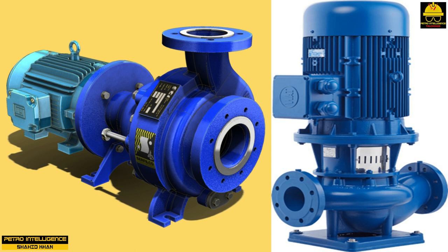Horizontal pumps are the most common type found in industry. However, vertical pumps are more compact, winterize better, and have a lower installation cost. Vertical pumps work well with liquids that are near their bubble point temperature. The lower impeller usually is located below ground level, which provides additional net positive suction head available, NPSHA. The terms horizontal and vertical refer to the position the shaft occupies in relation to the ground, as shown in the pictures. This direction indicates how impellers rest in the device.